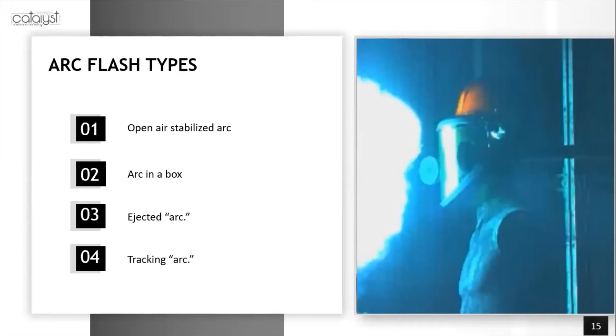Types of arc flash. So there's four main types. Most of what we talk about are open air and arc in a box. Ejected arc and tracking arc, they happen, but they're more rare. So open air stabilized arc, this is what it looks like. It could be conductors laying somewhere. There's a cover removed. So the flash can go really anywhere. The one that we most commonly see in industry would be this style here, where it's arc in a box. Typically you've had the cover off, and there's 5 sides that are directing all this energy at you while you've got the box open. That's what we would probably encounter the most.